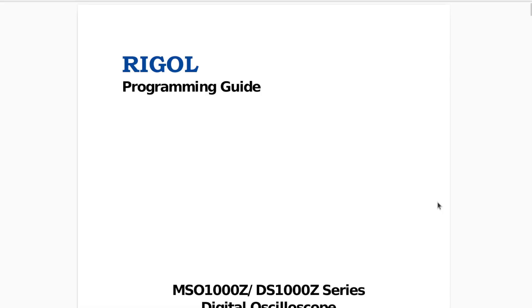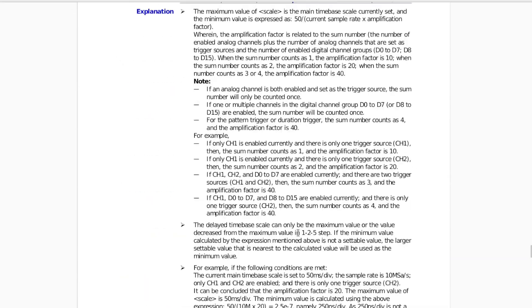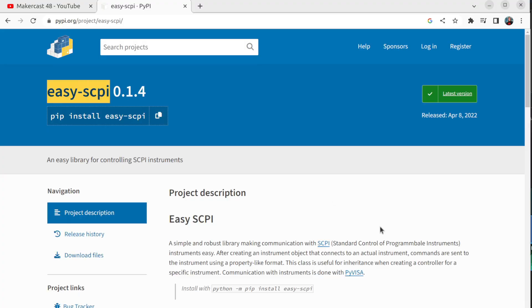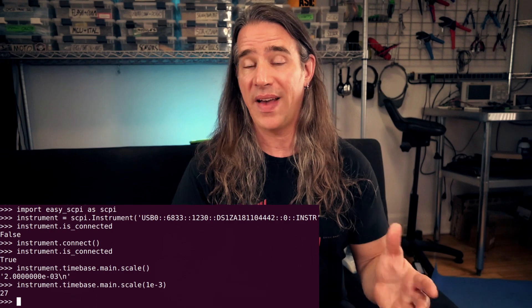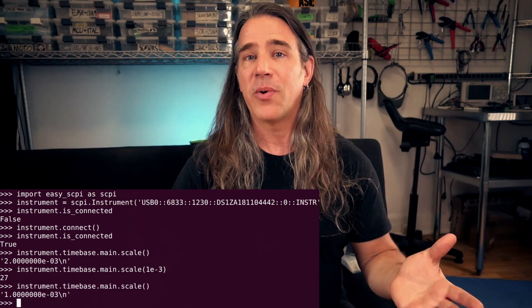The Rigol scopes have a nice API document, and you can use that to know which strings to write and how to interpret what you get back. This is all still pretty low level. One big step up for SCPI-supporting devices is the easy SCPI library. This thing is really sweet. It just uses Python's __getattr__ and call magic to instantiate properties dynamically and do querying, reading, and writing for you. The upshot is that you create an instrument with that same resource name, connect to it, and then just act like anything defined by the API hierarchy actually exists. So calling timebase.main.scale without a parameter is like querying for the value, and with a parameter, you're just writing to it. That's much cleaner and fun to use.